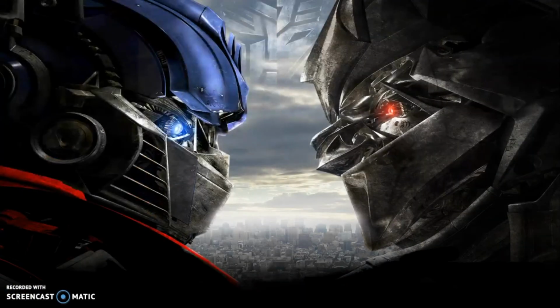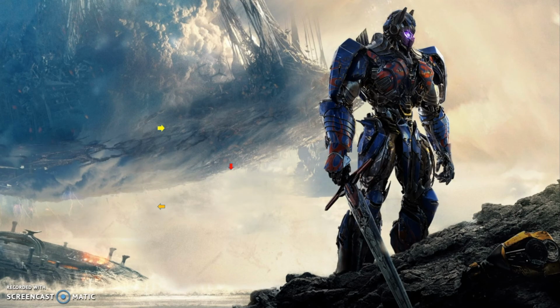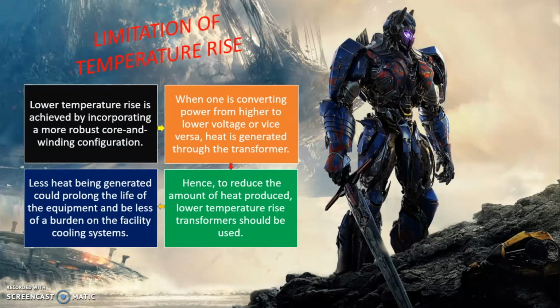Moving on, I'll talk about transformer modifications. One modification is the limitation of temperature rise, achieved by incorporating a more robust core and winding configuration. When converting power from higher to lower voltage or vice versa, heat is generated through the transformer. To reduce this heat, lower temperature rise transformers should be used. Less heat generated could prolong the life of the equipment and reduce the burden on facility cooling systems.